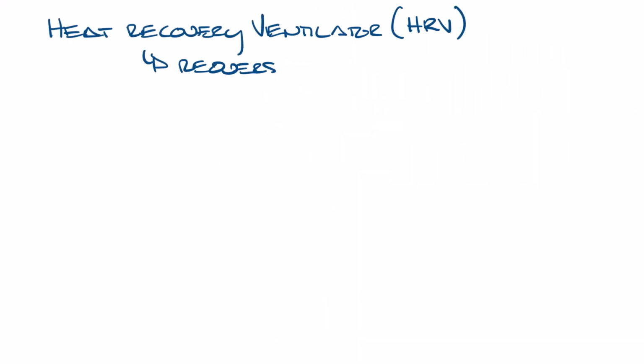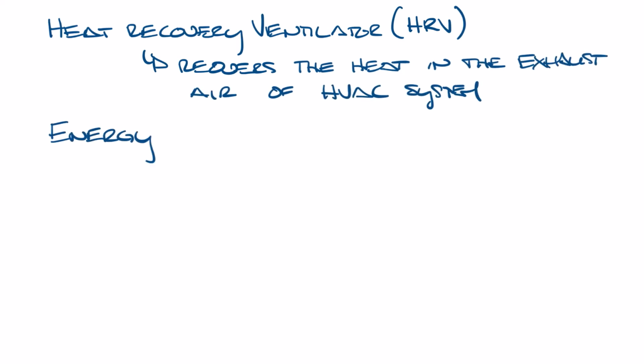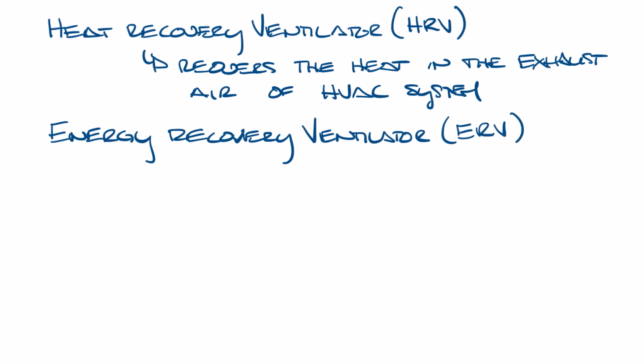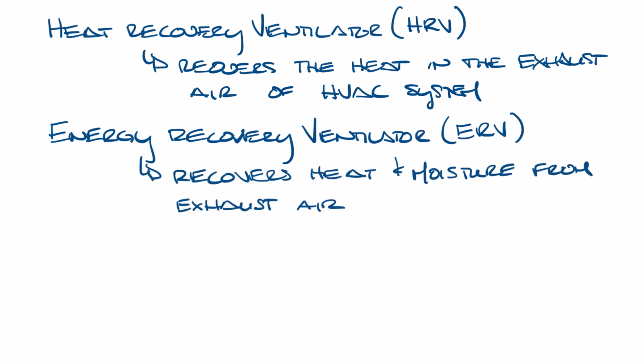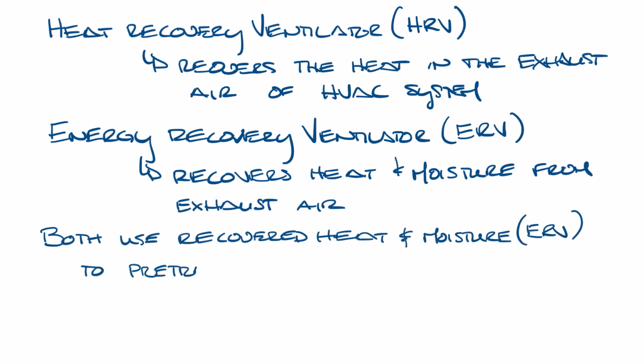So let's start with the difference. A heat recovery ventilator, or HRV, recovers the heat in the exhaust air of a building's HVAC system. An energy recovery ventilator, or ERV, recovers the heat and moisture in the exhaust air. They both use this recovered heat and moisture to pre-treat the incoming ventilation air.